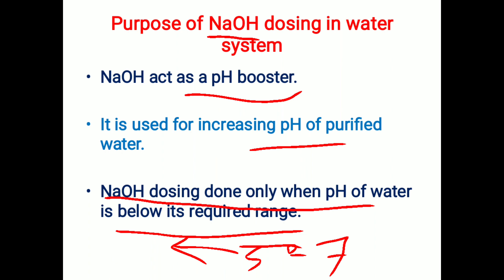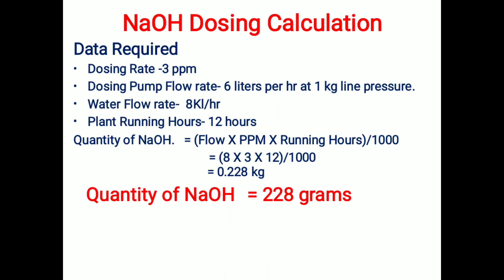Now we'll see how to do the dosing calculation. The data required for dosing calculation: first, the dosing rate — here I have taken 3 ppm. Second, we need the specification of the dosing pump through which we are going to make the dosing — here the dosing pump is 6 liters per hour at 1 kg line pressure.